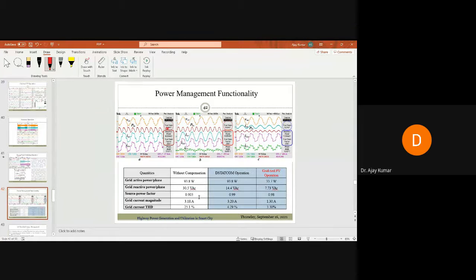After incorporation of the D-STATCOM or the inverter, the active power remains similar, reactive power is reduced to 14.4 kVAR, and the power factor is improved to 0.99. After implementing the solar photovoltaic system, reactive power is further reduced because power is shared between the grid and the solar photovoltaic system, and the power factor rises to the range of 0.98 or 0.99. So this is the overall comparison of without compensation, D-STATCOM operation, and grid-tied PV operation — the multifunctional operation of this multifunctional inverter.